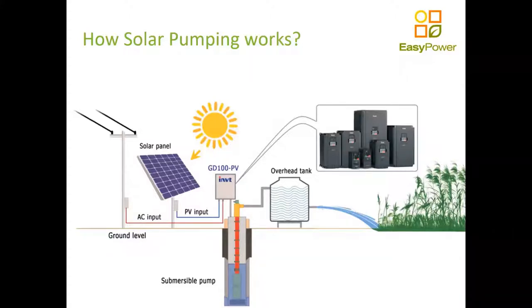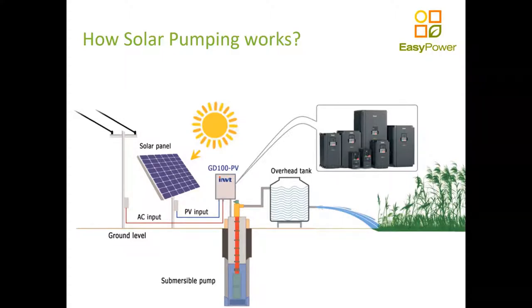An important element in this diagram is the overhead tank — not necessarily in every application, but highly recommended. Your overhead tank is your battery. If you need to irrigate 24 hours a day, oversize your system so you can pump during four or five hours a day enough water for a 24-hour period into an elevated tank — you've essentially created your own battery. Potential energy in the tank will supply the pressure to your system. This could be a small dam on top of a hill, or a couple of tanks. That solution is much less expensive and more reliable than having a battery system.